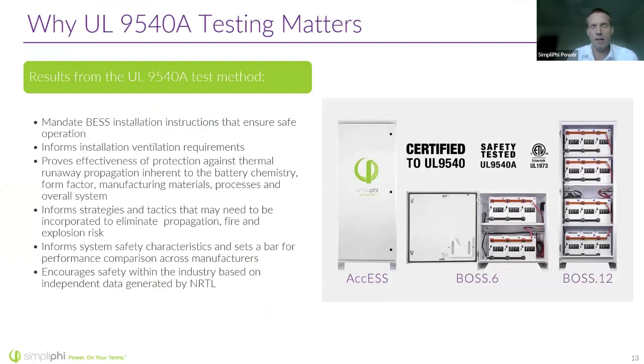Let's get into why the UL certification matters. It's often mandated, so installers are simply having to follow local rules and guidelines. The UL 9540A test method informs things like ventilation, since batteries can give off harmful gases if they catch fire. We want to make sure we monitor those and install things in a safe way.